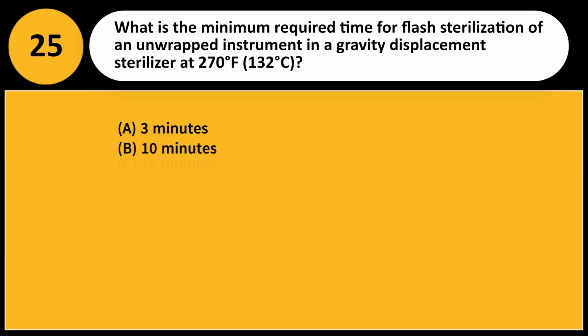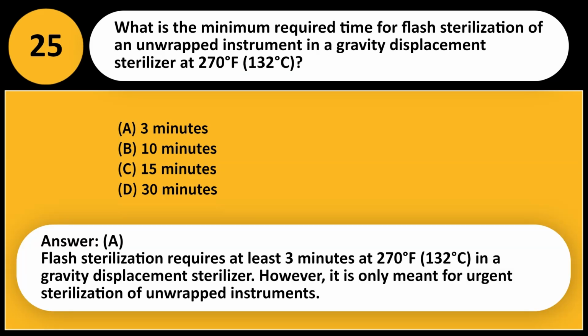What is the minimum required time for flash sterilization of an unwrapped instrument in a gravity displacement sterilizer at 270 degrees Fahrenheit, 132 degrees Celsius? A. 3 minutes. B. 10 minutes. C. 15 minutes. D. 30 minutes. Answer: A. Flash sterilization requires at least 3 minutes at 270 degrees Fahrenheit, 132 degrees Celsius in a gravity displacement sterilizer. However, it is only meant for urgent sterilization of unwrapped instruments.